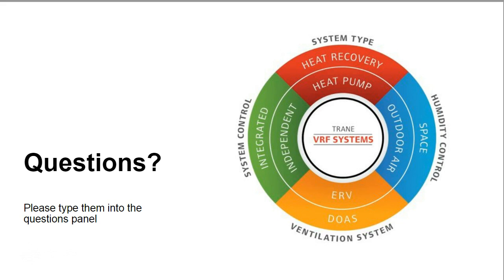Somebody asked, the refrigerant line lengths vary depending on whether the outdoor unit is above or below the indoor units, correct? That is correct. So depending on whether you're placing the outdoor unit above or below the branch circuit controller, you will be limited to the line length limits per each VRF manufacturer. And this is mostly due to the amount of work that's able to be done by the VRF compressors.